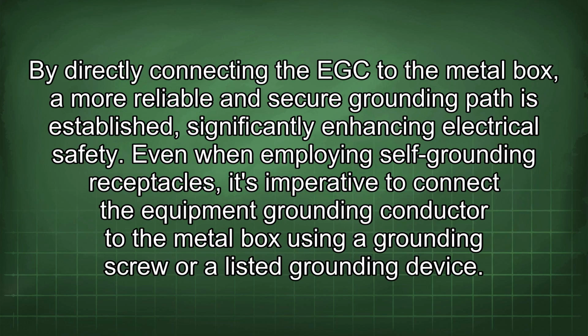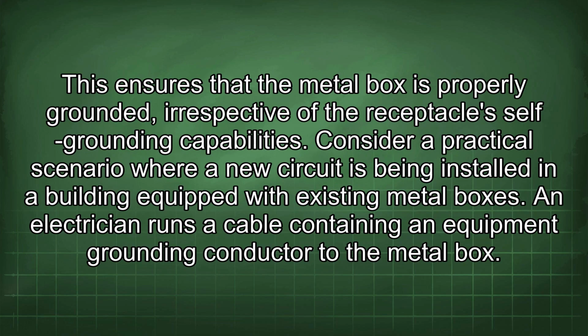By directly connecting the EGC to the metal box, a more reliable and secure grounding path is established, significantly enhancing electrical safety. Even when employing self-grounding receptacles, it's imperative to connect the equipment grounding conductor to the metal box using a grounding screw or a listed grounding device. This ensures that the metal box is properly grounded, irrespective of the receptacle's self-grounding capabilities.